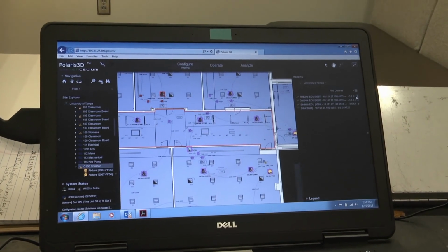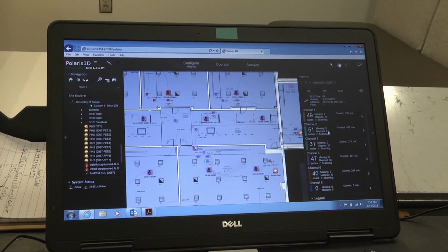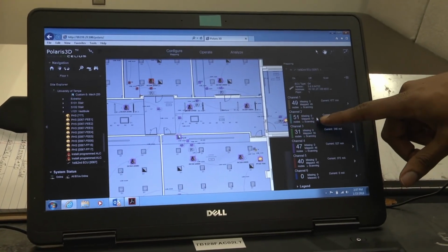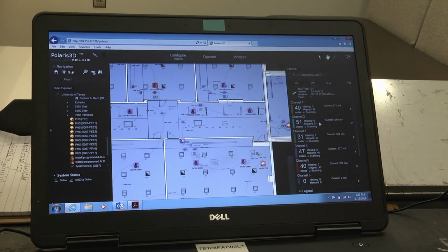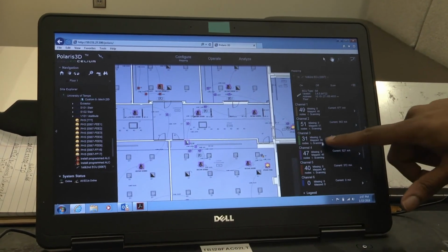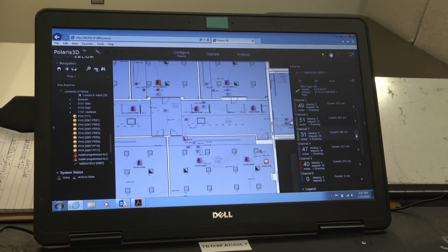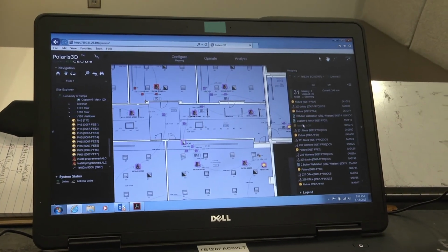All right, so that was first floor ECU. Okay. So you can look at the counts, right? So you see how many devices and how many are mapped. These should match. If they don't match, then that means there is something not mapped. So this one here is 30 and 31, so one is not mapped. So if you open that ECU by clicking on the arrow to the side, and then scroll through right there.